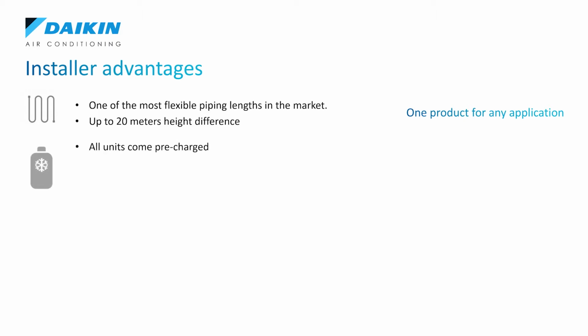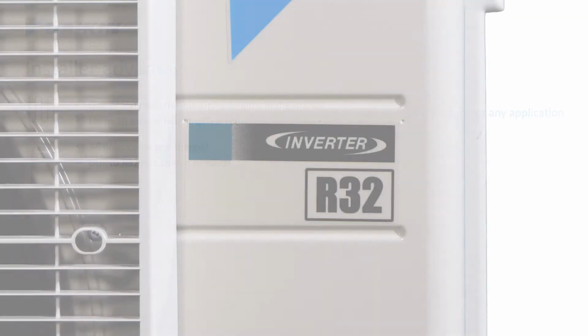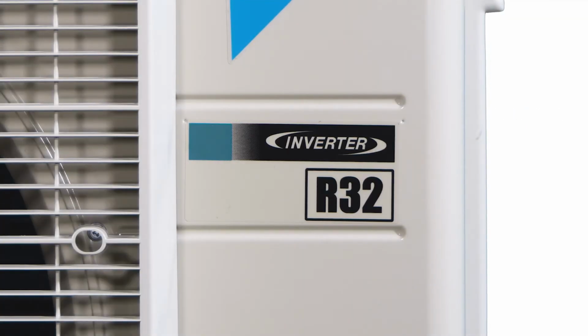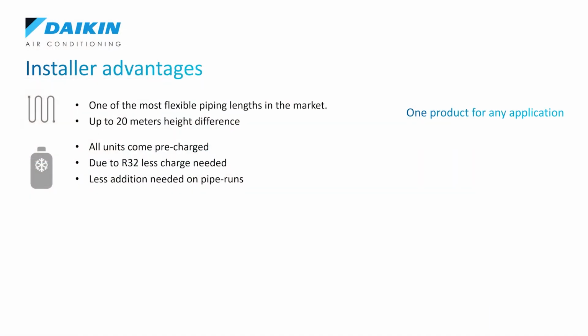This Sensira also saves you on installation cost. All our units are pre-charged for up to 10 meters. Due to R32 in the system, you require less charge and less refrigerant addition on extended pipe runs. And of course, as earlier mentioned, R32 is much easier to handle as it is only one component.